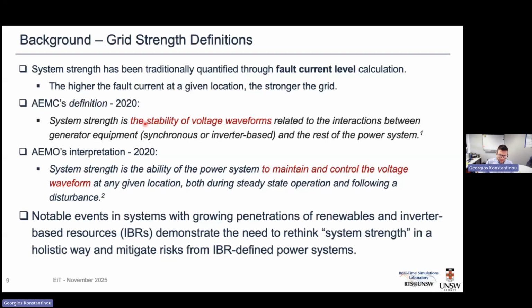So locally in Australia, we use the definition of system strength that AEMO initially defined in 2020, which is the ability of the power system to maintain and control the voltage waveform at any given location. The explanation is that this needs to happen both under steady state operation and also following disturbances. So the fault current level might give you some indications of what to expect, but the reality is that we need to understand what could impact the voltage waveform at a particular location, and how well we can regulate this voltage waveform under steady state and also during transients.